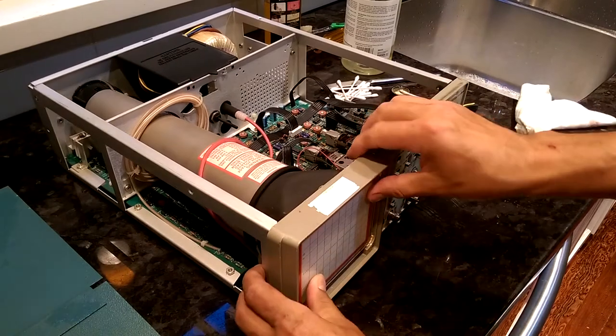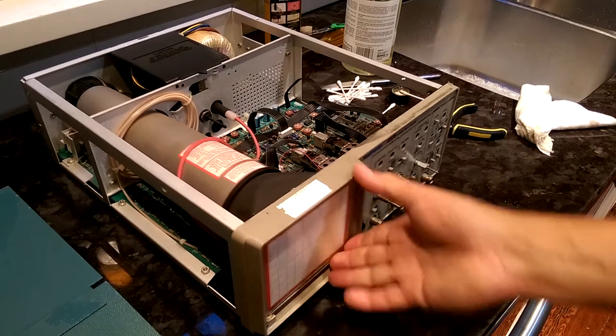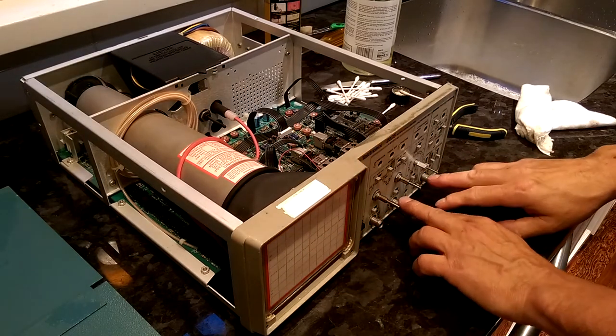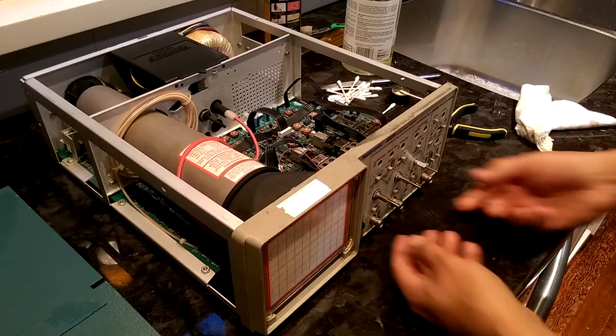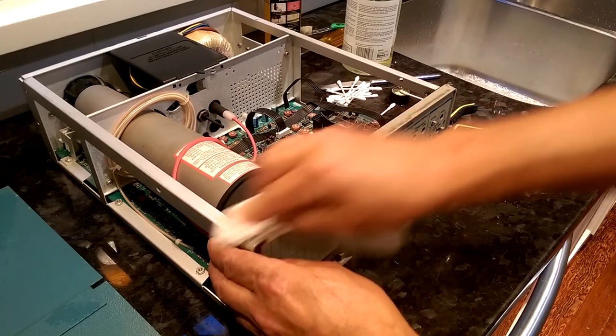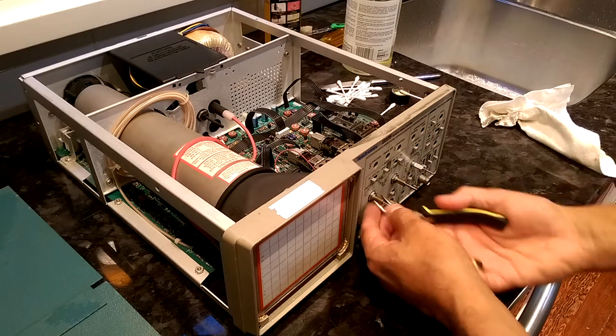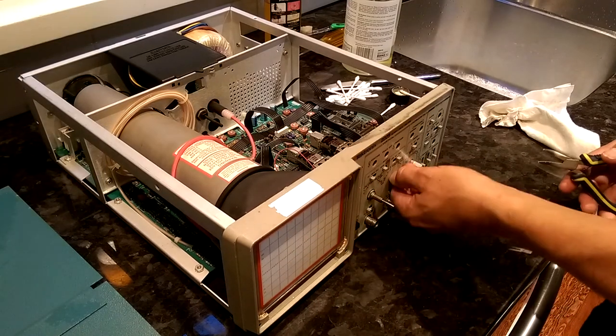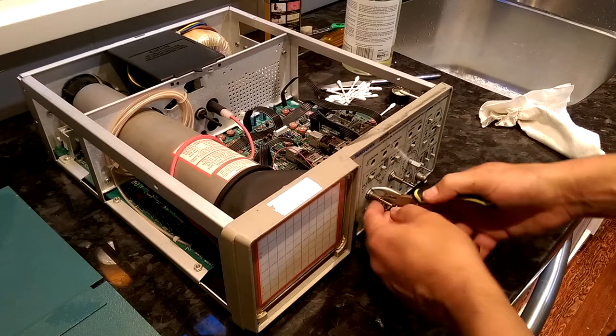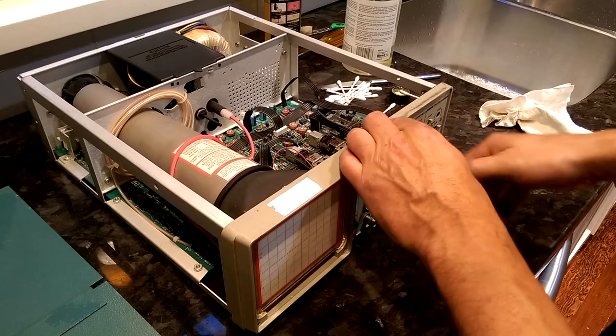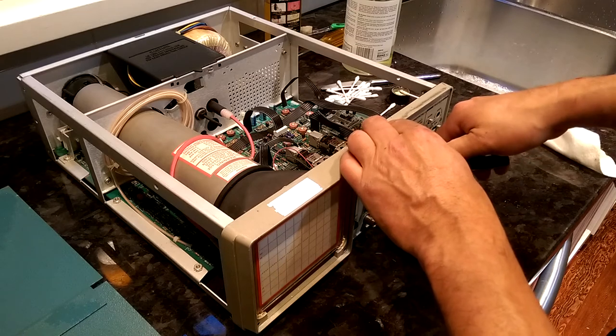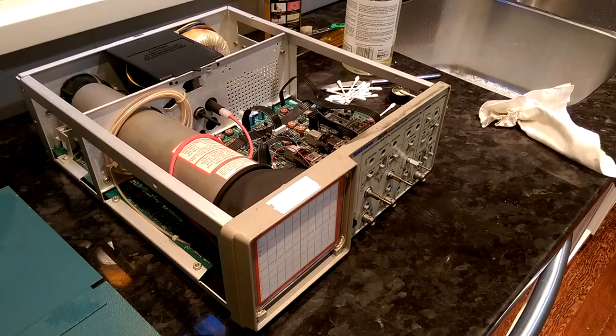So indeed, it does look like the only way to get at the faceplate is to take this out and perhaps desolder the BNC connectors on the front. Alright, so I have decided that that is not worth my effort to try and do at this point. So we're just going to go back to cleaning the front panel carefully with the knobs removed and then we will clean the knobs thoroughly and reinstall them on the scope.